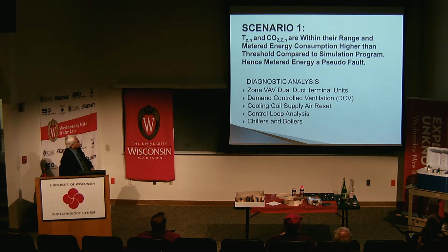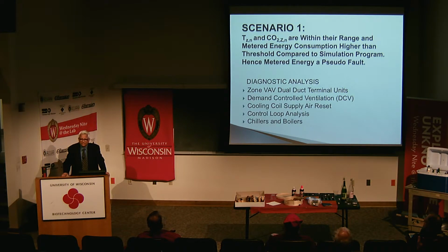Now, let us take a look at temperature and CO2 in the room. If both are within the range, normally we would say, why bother? Nothing to bother. No, that's not true. If you look at the metered energy consumption, and compare it with the simulation program with a threshold, maybe you want to say the metered energy consumption should not be more than the simulation program by, say, 8%. If it's high, then I call the metered energy consumption a pseudo fault. I'm introducing a new term called pseudo fault. In other words, the metered energy consumption, nothing wrong with it. It is accurate. But when you compare with a benchmark, it's not accurate. So I call it a pseudo fault.